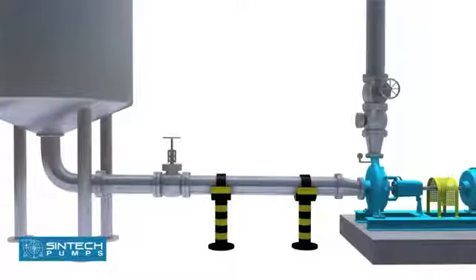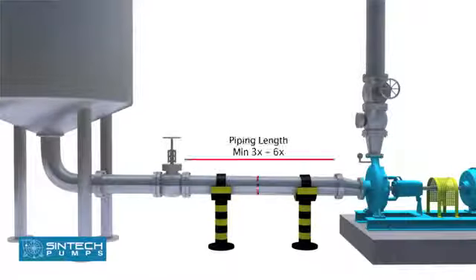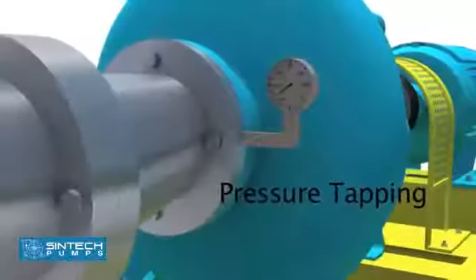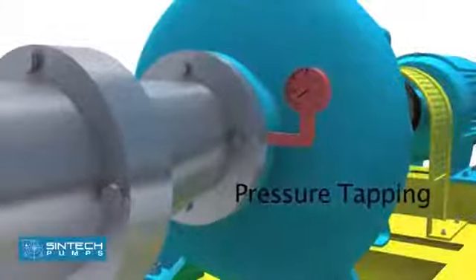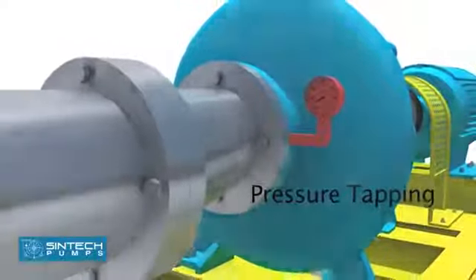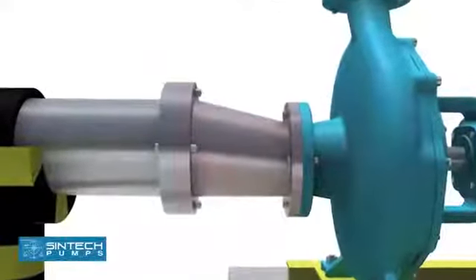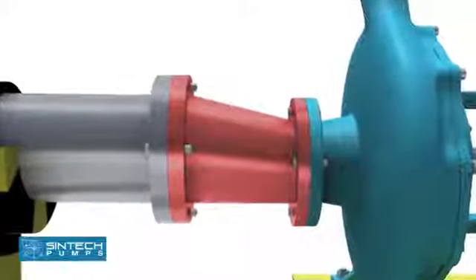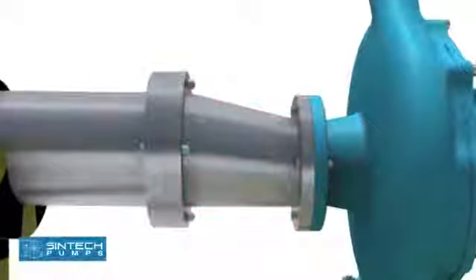The straight run of piping leading to the pump suction nozzle should be at least 3 to 6 times the diameter of the pipe from the upstream elbow. The suction pipe should be sized to ensure liquid velocity of not more than 3 meters per second. There should be a tapping provided for installing a pressure gauge in the suction line. The reducer should be an eccentric reducer with the flat side as the top side.